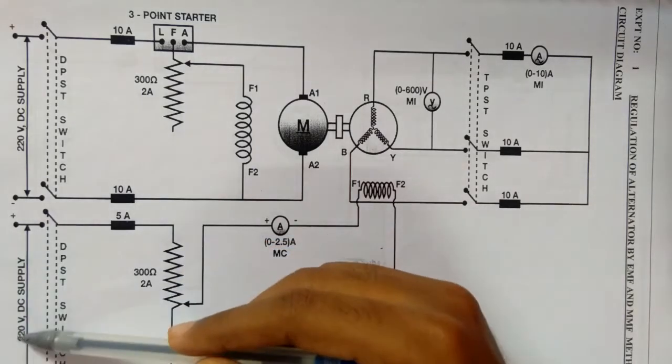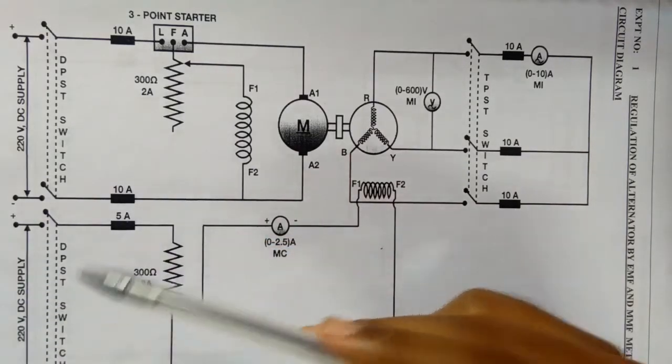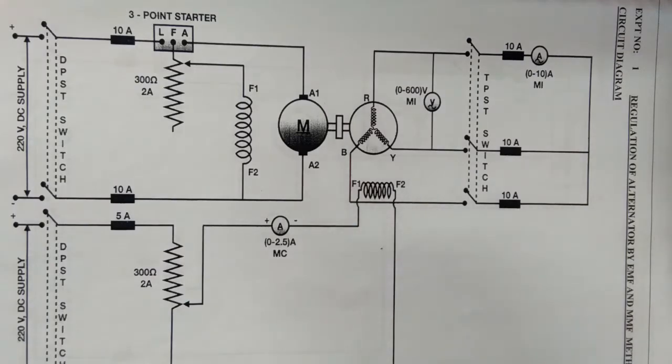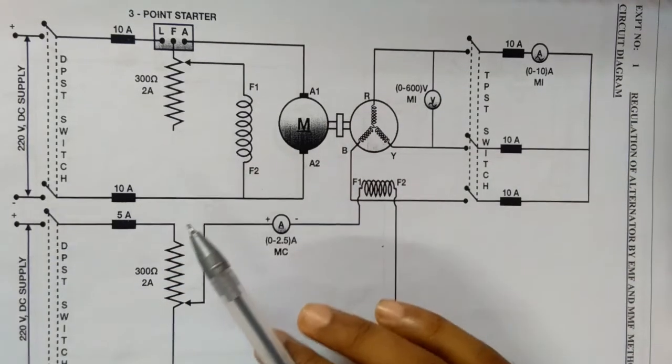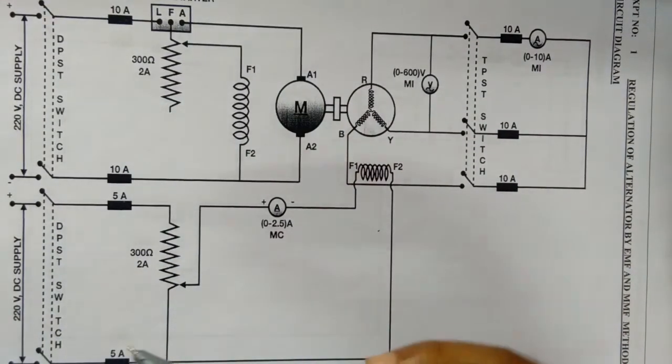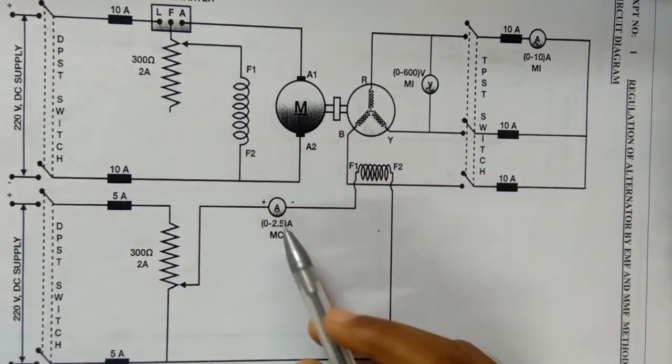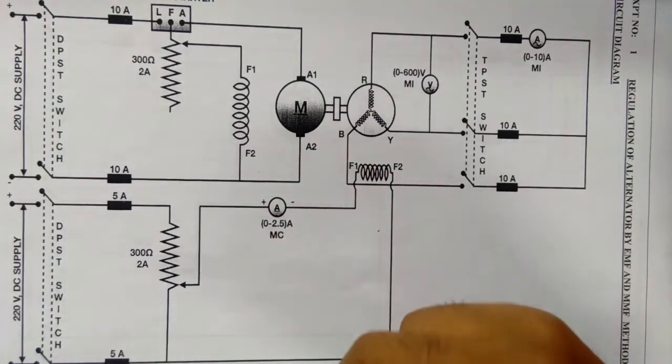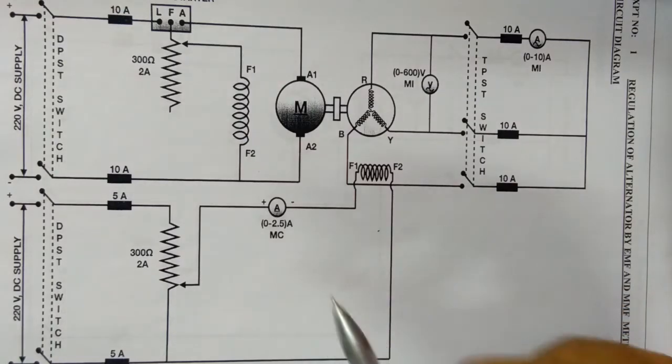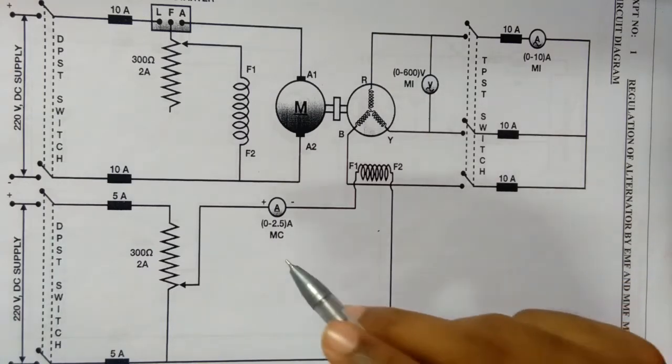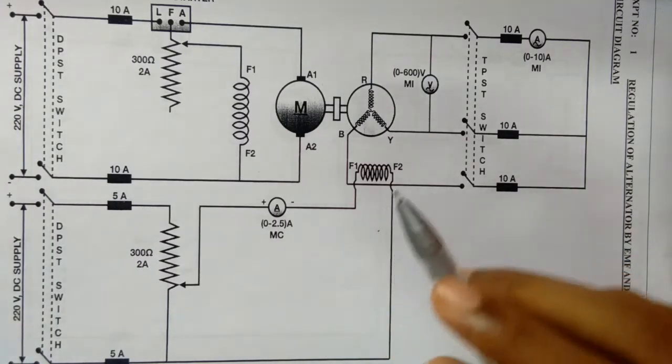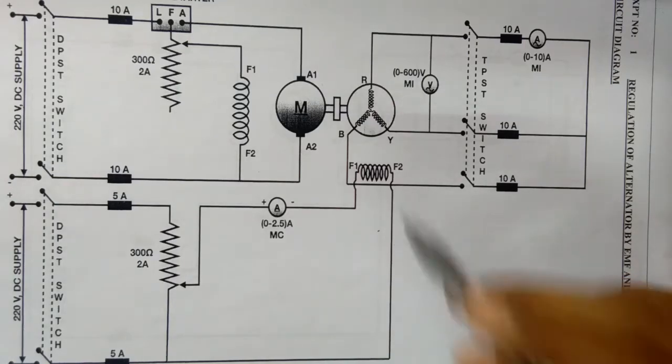220V DC supply is switched on to the field winding of the alternator by closing the corresponding DPST switch. So for the OC test using the potential divider, current in the field circuit is increased in the step of 0.1 Ampere. Under each step, the alternator induced voltage indicated by the voltmeter and the corresponding field current IF are noted down. This procedure is continued till the alternator voltage is 110% of its rated voltage.